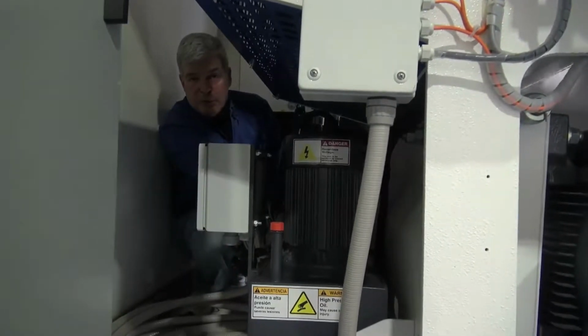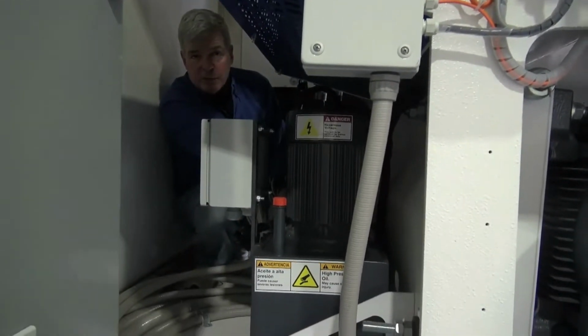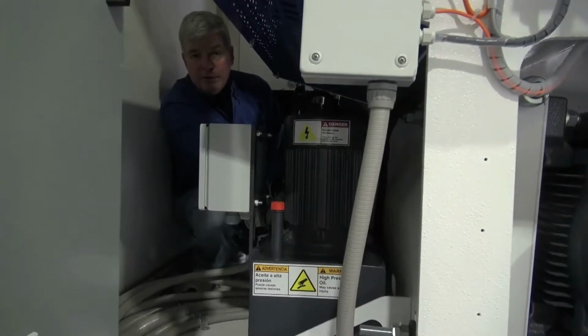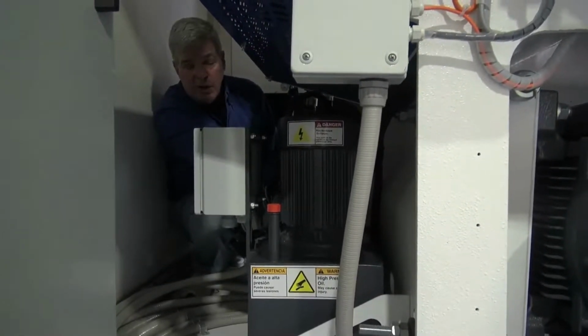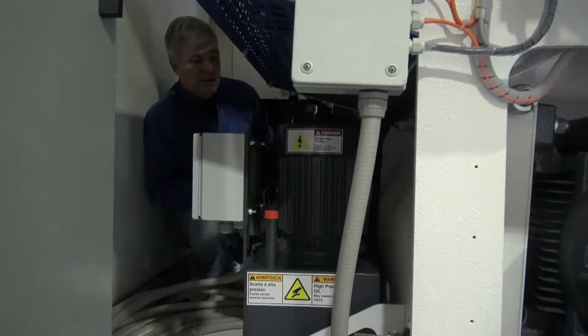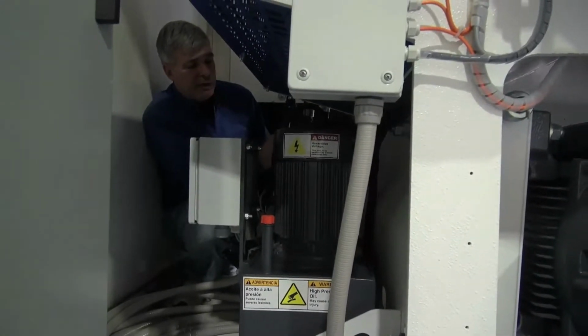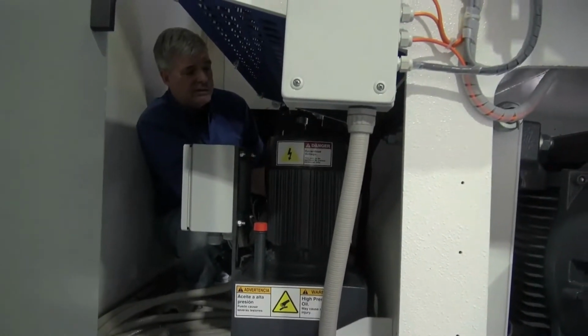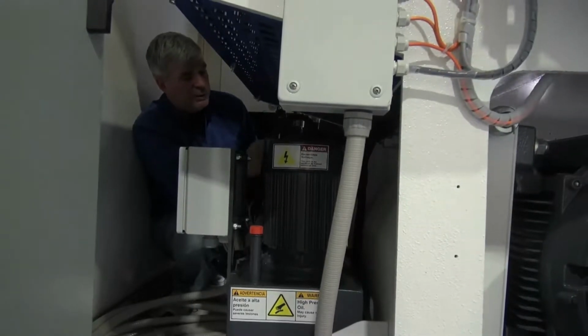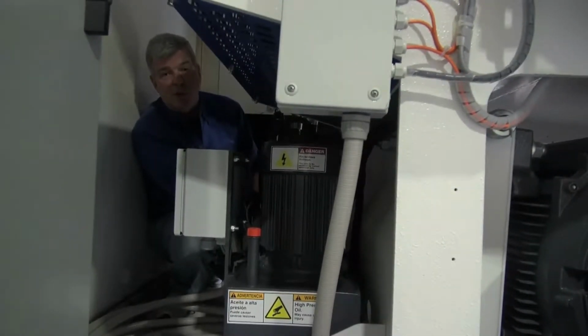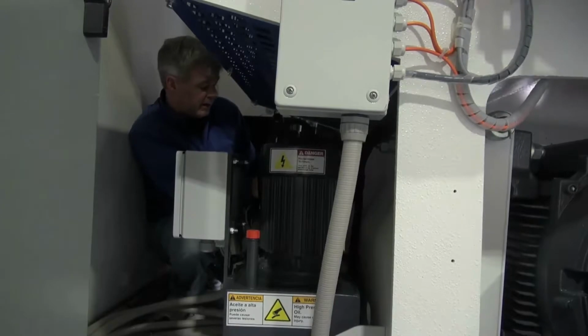There's a temp level switch in this hydraulic pack that will turn the machine off if the oil gets too hot or the level gets low. There also is a pressure gauge. This pressure gauge has a tap at the bottom. We recommend during operation that this tap is closed and only open for diagnostic purposes.